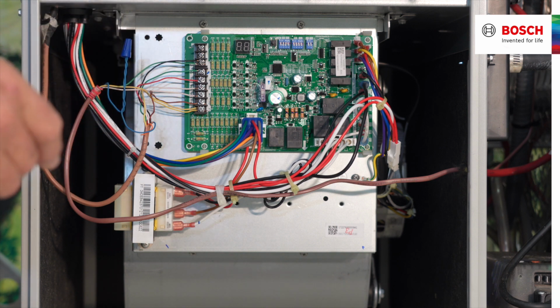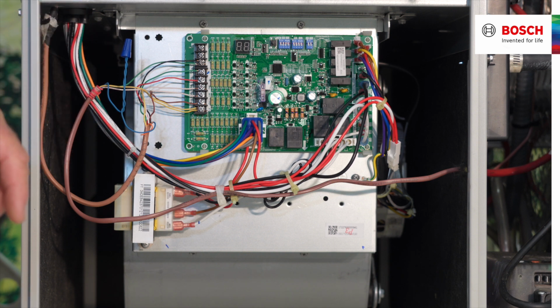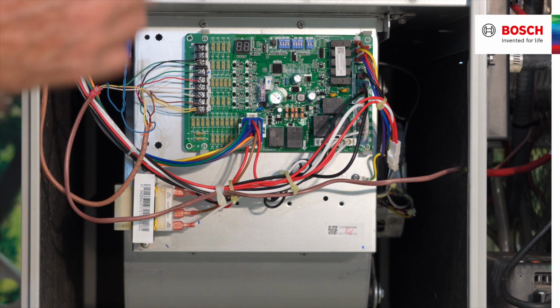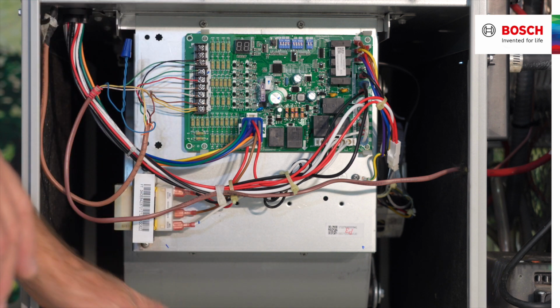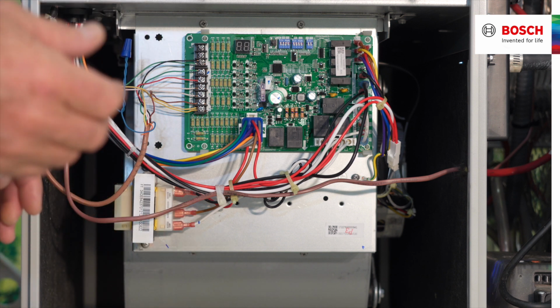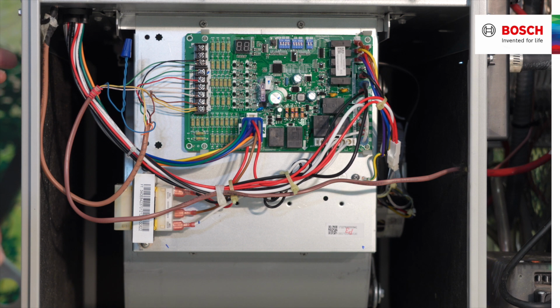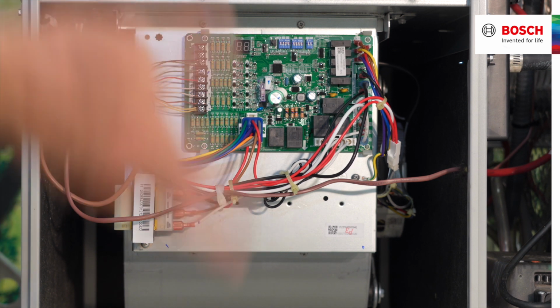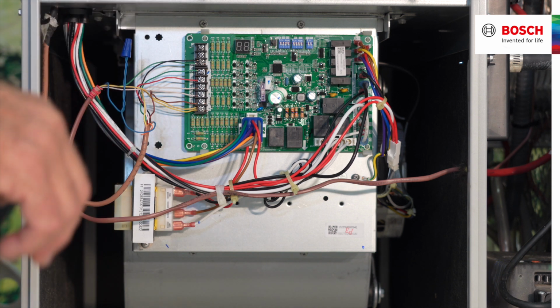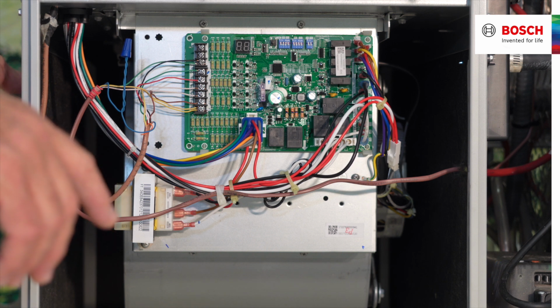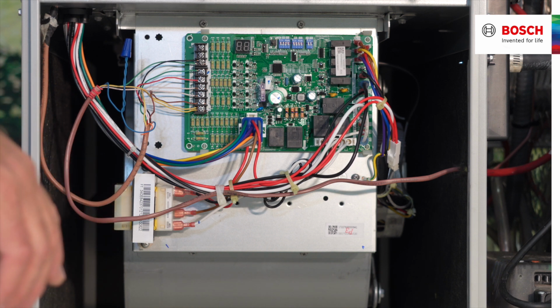Remember that I can set the board up CFM wise. Remember that we can set the board up to have a W1, W2 off of a time mechanism if we don't have enough wires coming from the thermostat to operate that W1, W2. But again, very, very sealed compartment. Another thing that we want to make sure that you understand is that in a 5-ton application, we're going to have a box that is maybe sitting in a basement, and we're not using the bottom plate for return. Your installation manual says that both sides of this box will have to be taken away for the return, and so you're not going to be able to get enough return air through one side. So it's on the 5-ton system only.